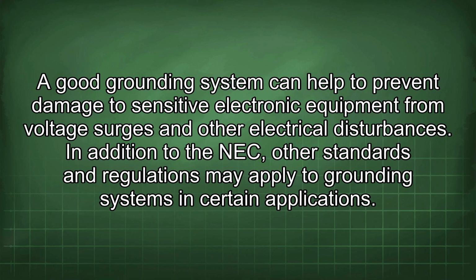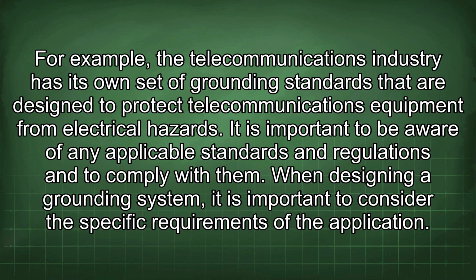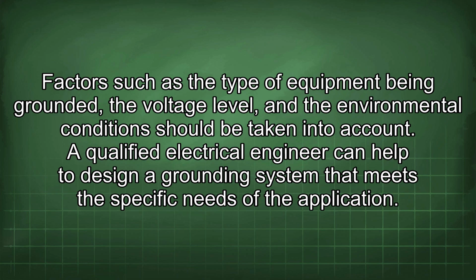In addition to the NEC, other standards and regulations may apply to grounding systems in certain applications. For example, the telecommunications industry has its own set of grounding standards that are designed to protect telecommunications equipment from electrical hazards. It is important to be aware of any applicable standards and regulations and to comply with them. When designing a grounding system, it is important to consider the specific requirements of the application. Factors such as the type of equipment being grounded, the voltage level, and the environmental conditions should be taken into account. A qualified electrical engineer can help to design a grounding system that meets the specific needs of the application.